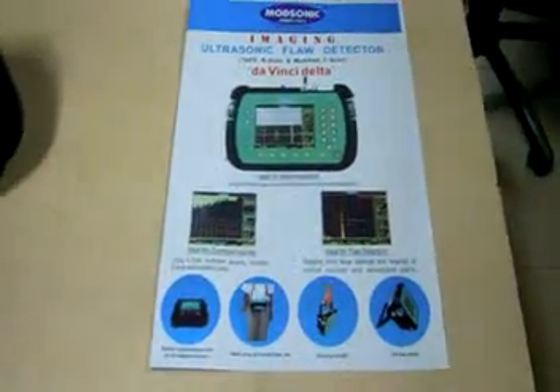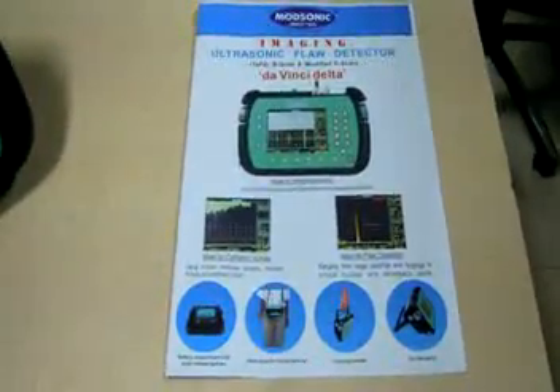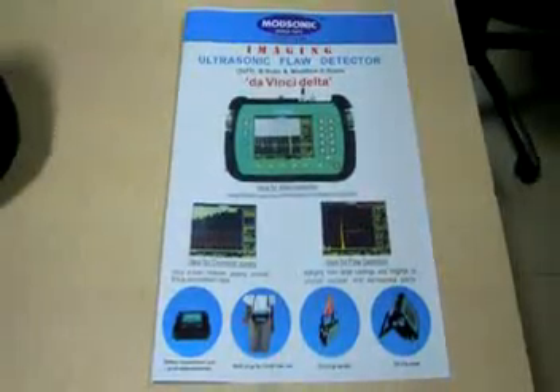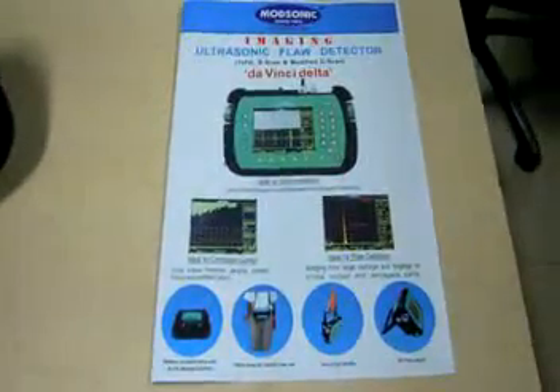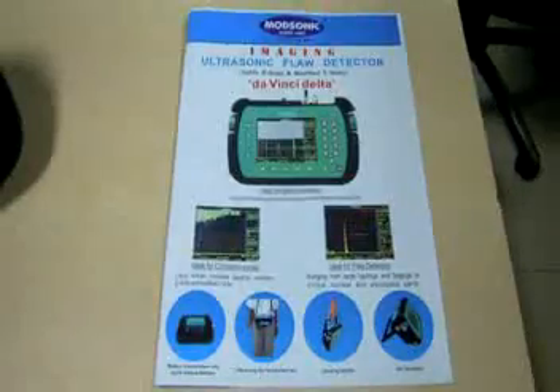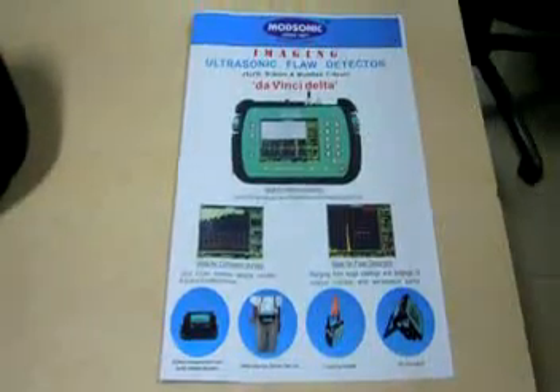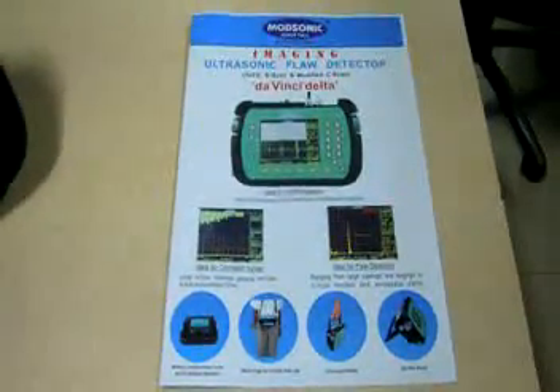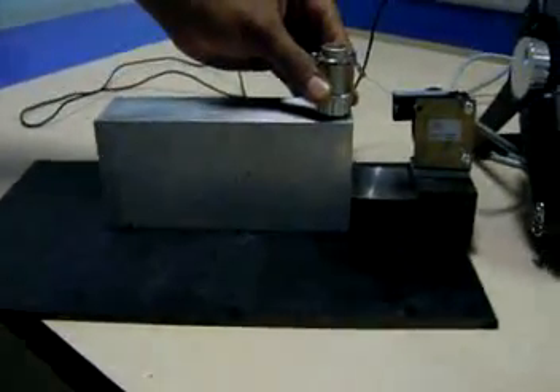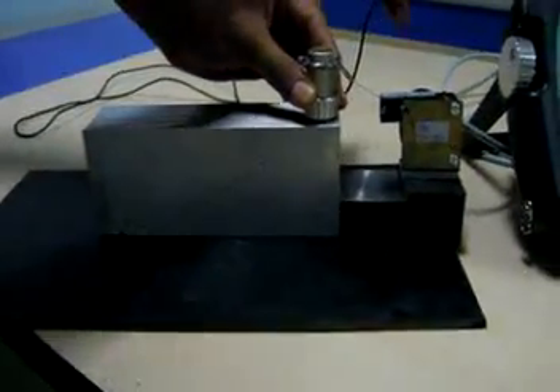We are going to demonstrate B-scan ultrasonic flaw detection application on Da Vinci Delta ultrasonic flaw detector designed and manufactured by Modsonic India. So now we will see that there is an aluminum block with the holes and slots on the left side, and we are going to use a single crystal normal probe.